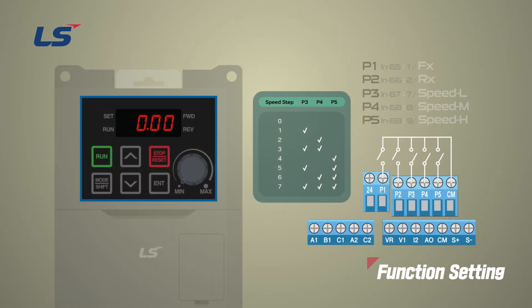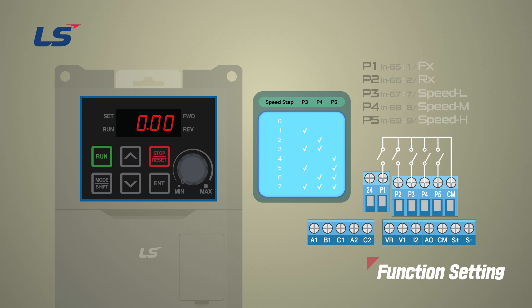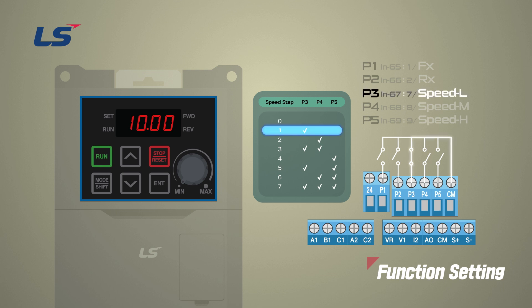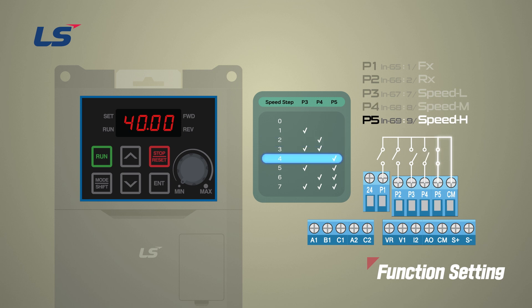Depending on the input sequence of digital input speed L, M, and H, the multi-step operation works in a binary sequence. You can check the input sequence for each stage through the IN90 DI status parameter. When the multi-speed frequency P3 terminal — speed L — is turned on, the first stage is activated. When the P4 terminal — speed M — is turned on, it is the second stage. When the P5 terminal — speed H — is turned on, it is the fourth stage.